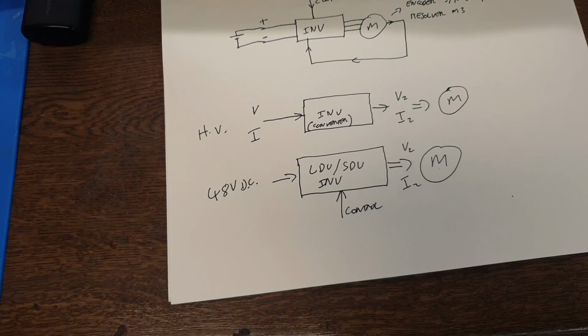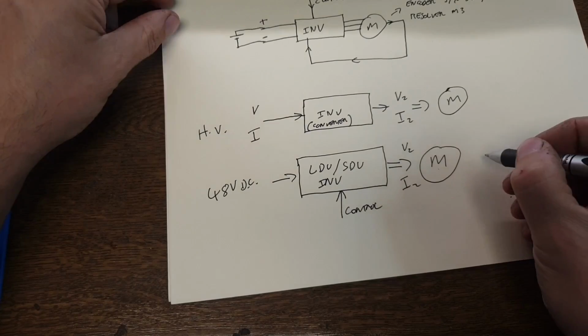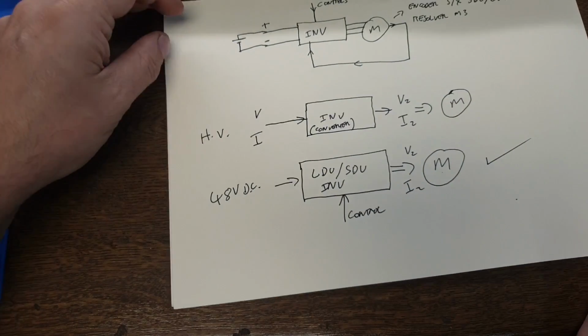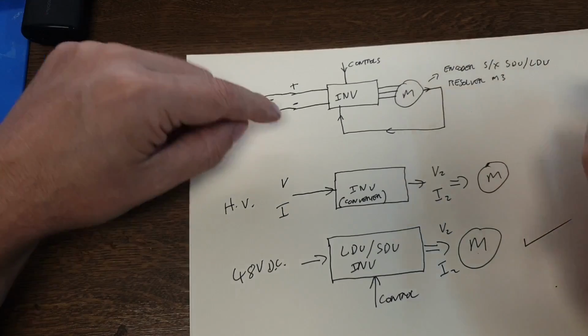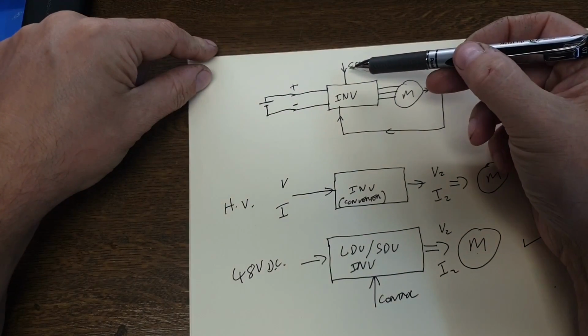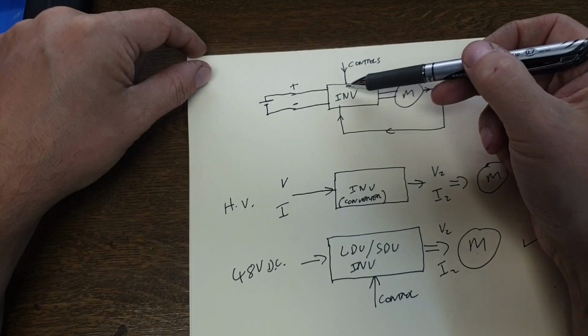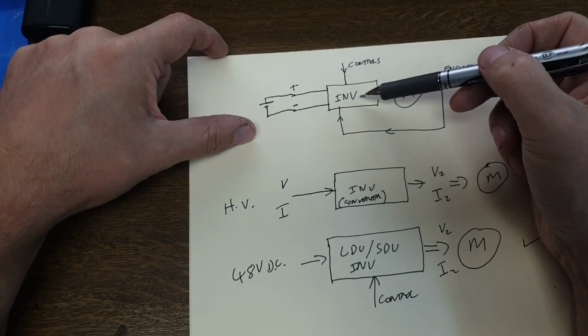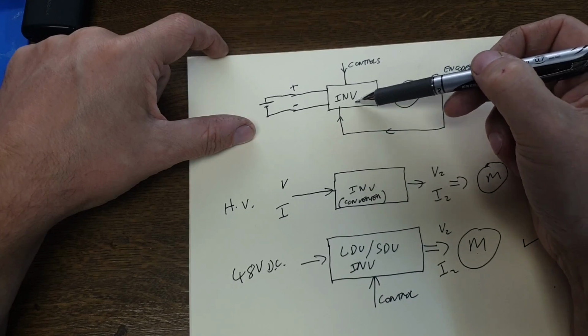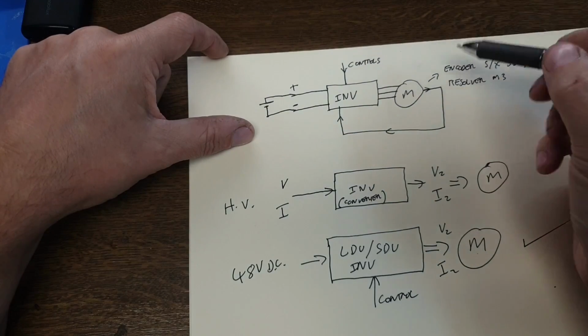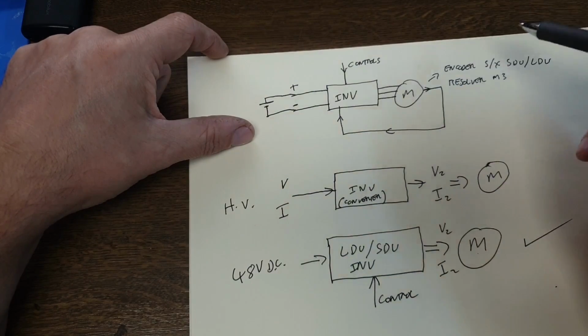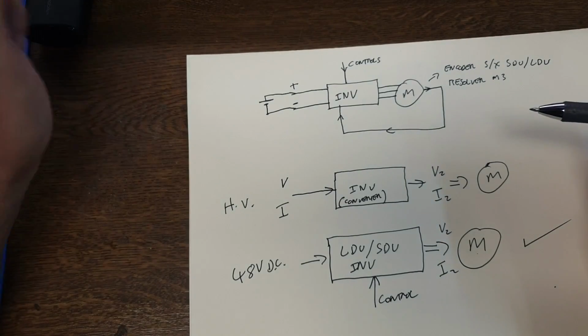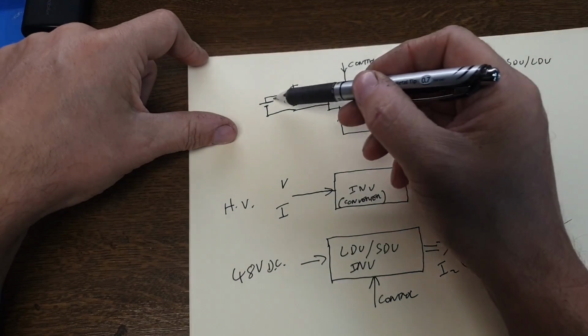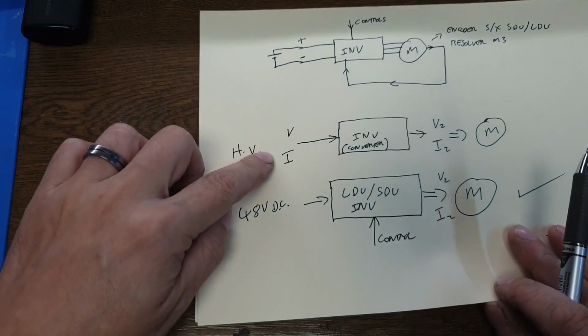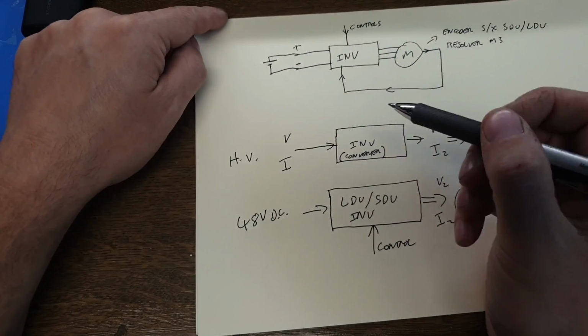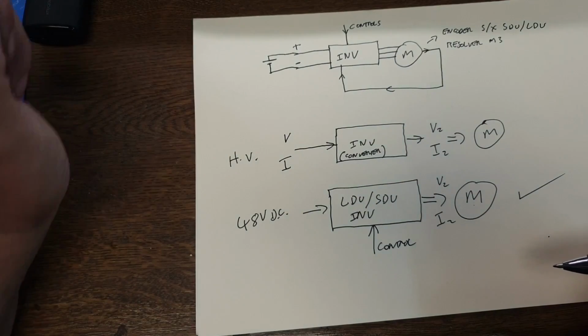It'll happily do that, assuming everything is doing what it needs to do: that our control signals are correct, the hardware and software configuration of the logic board is correct, the position signal from the encoder or resolver is correct, and we have sufficient voltage and current supplied to the input side of our inverter.